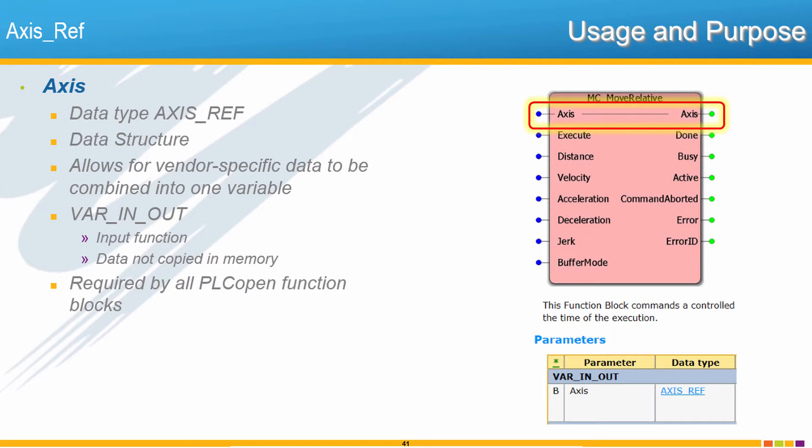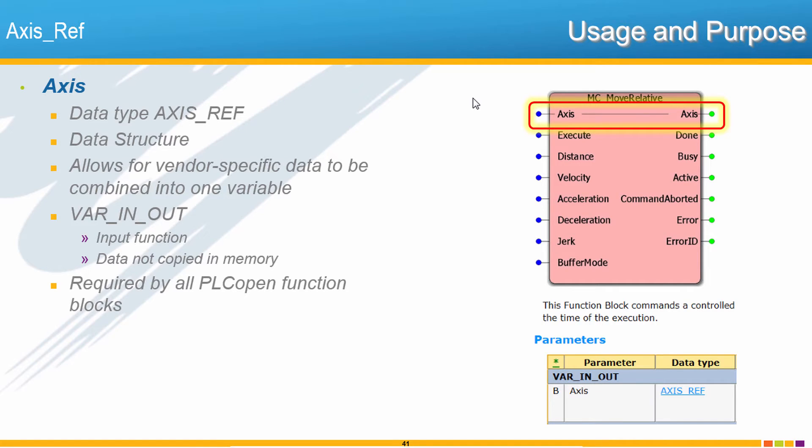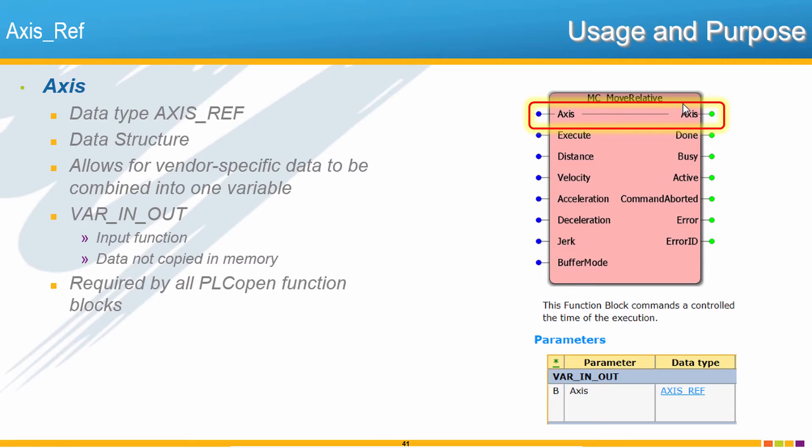If you look at any of the PLCopen function blocks, they all have one thing in common, and that is that this top connection is for this axis variable. The variable it's looking for is a data structure with the axisRef data type. AxisRef is a structure that is individually defined by each manufacturer who implements PLCopen, and it could contain a large amount of data. So to save memory in the controller, PLCopen defines that axisRef is not an input variable but instead a var in out.